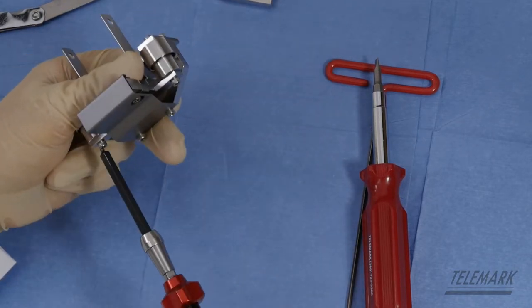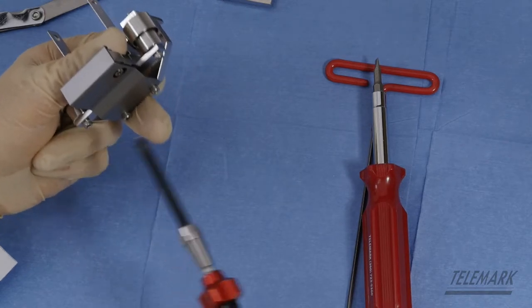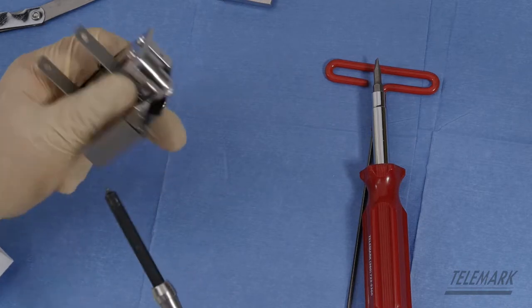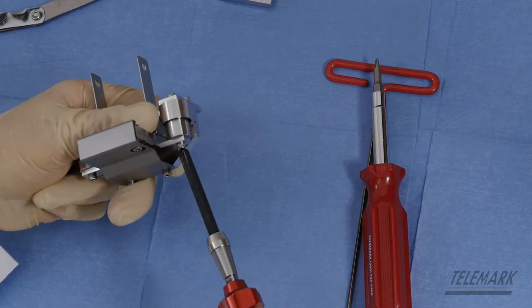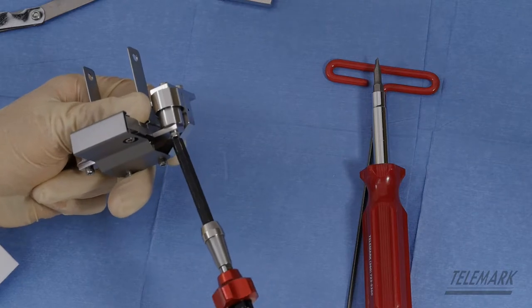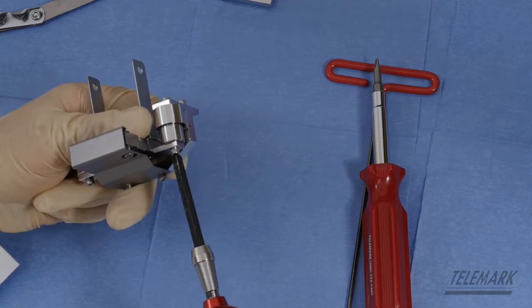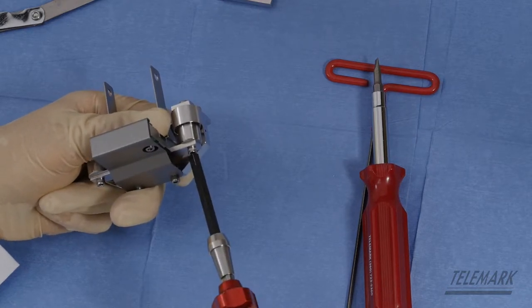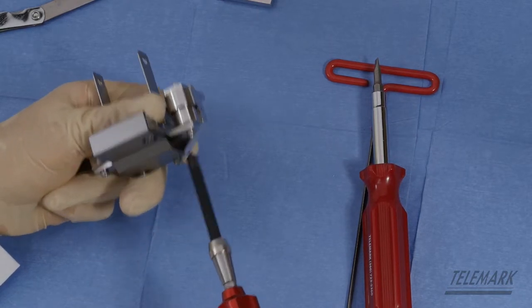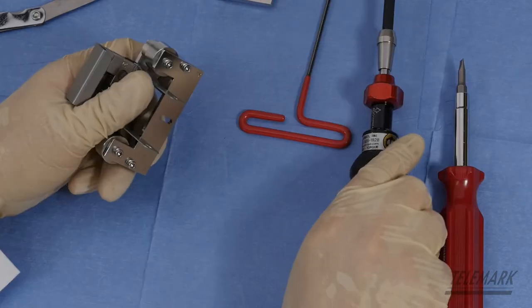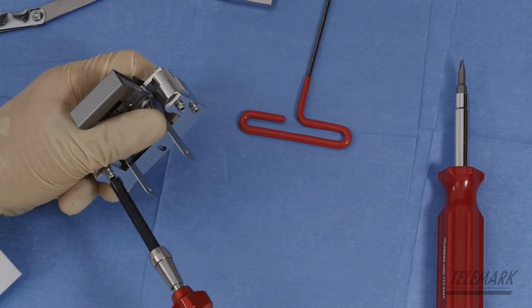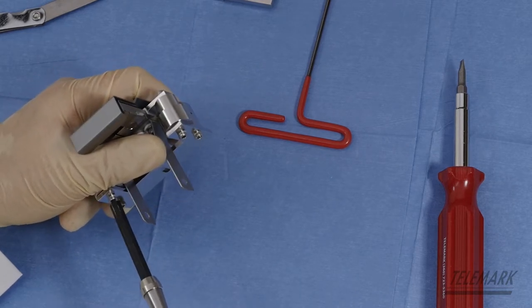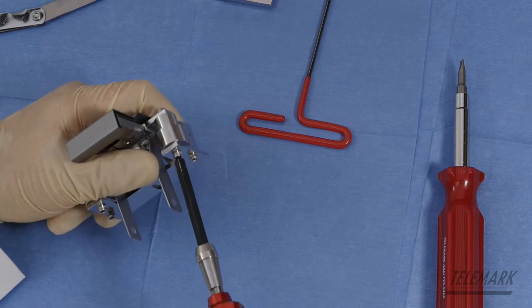You probably have to do this multiple times. You want to lock that one down while pushing your thumb across the bus bars, and this one doesn't want to cooperate, which happens once in a while. Then go back and snug those down with your torque wrench.